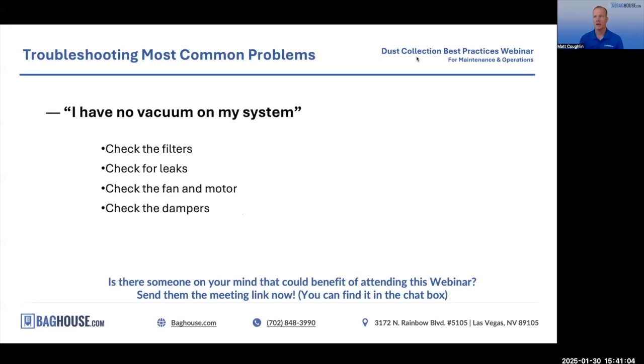But what happens over time? Something we see almost everywhere we go. That system changes over time. Someone has decided at some point to add a machine, or we're going to close this branch here. We're going to move it over there. All those little changes that seem fairly innocuous, they add up and they change the static pressure of your ductwork, and they will add a branch here. Now your airflow requirements have changed.